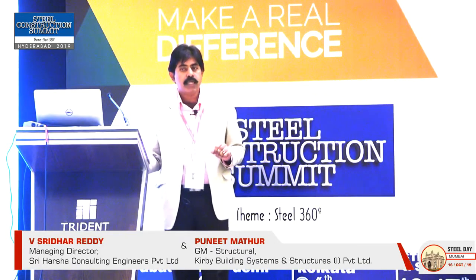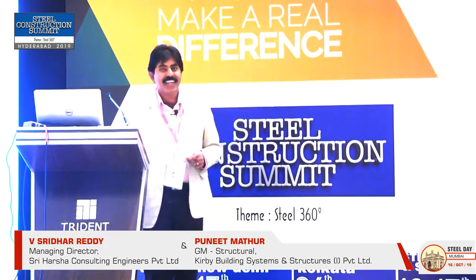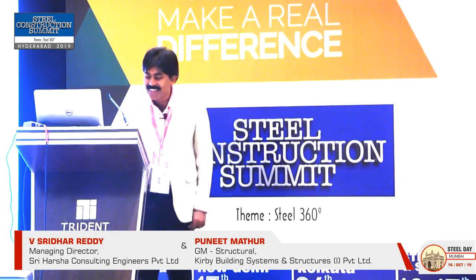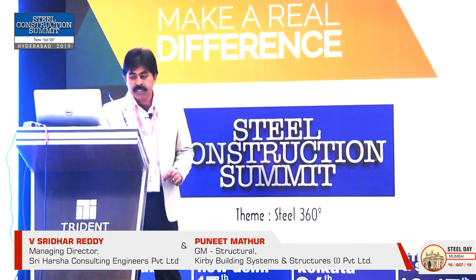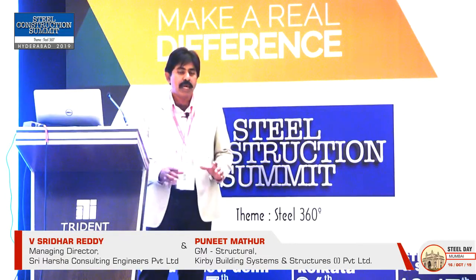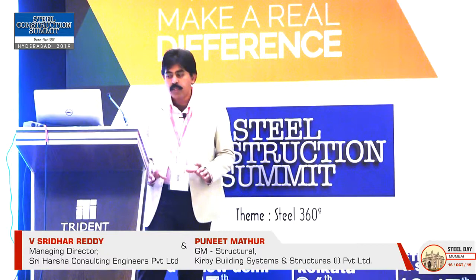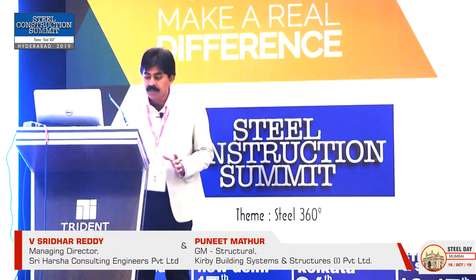So as per the code, we have to go for 400 kg per square meter — codal guidelines require that. This data center is a very large live load complex: it is going to be 1,800 kg per square meter as a UDL. And each rack is going to weigh 2.5 tons — that is a very huge load.